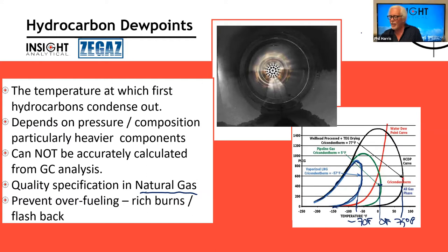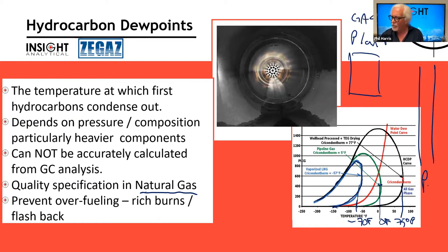Yeah, that's a good question. So we end up in this situation that I have my gas plant over here. It's my natural gas processing facility. I have my pipeline over here. And at some place, it moves across out of the plant and into the pipeline, right? And so there's a custody transfer point that happens there. So the gas plant, if it wants to make sure it's operating well, is going to put an analyzer over here. And so to Dale's point, the pipeline operator gets to put a specification on it. It says, I don't want your hydrocarbon dew point any higher than minus 15 degrees C.